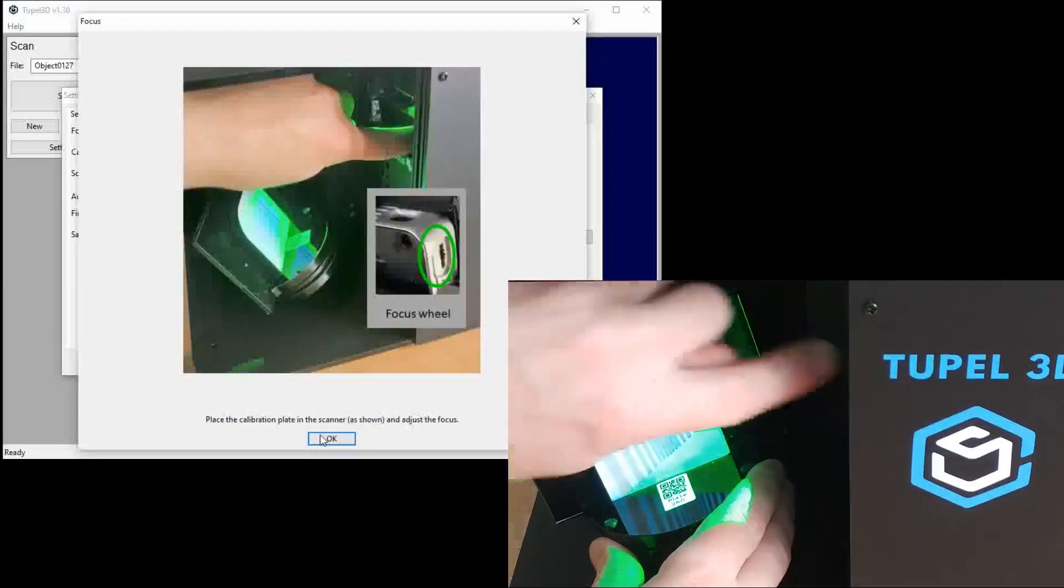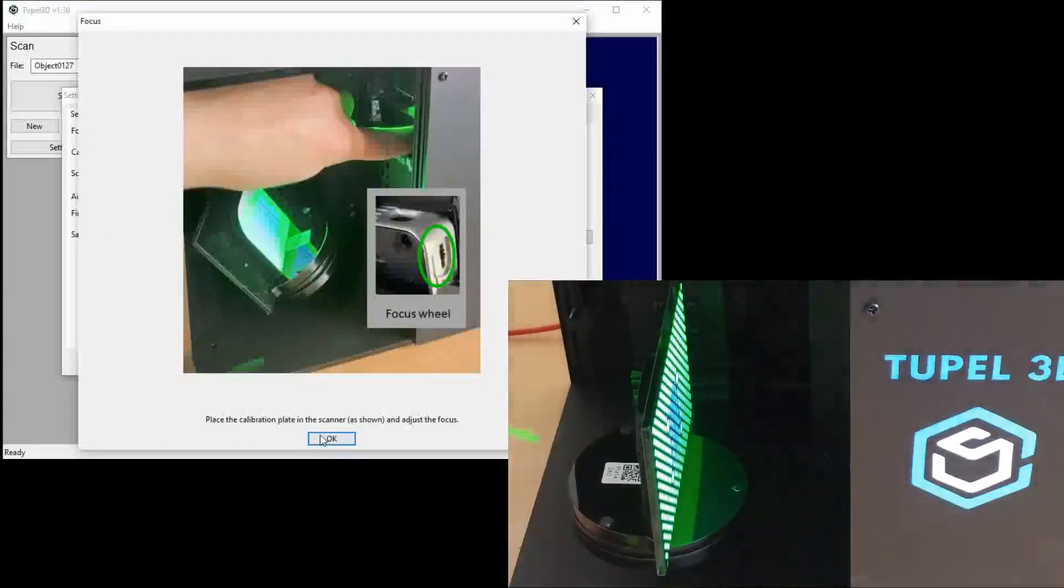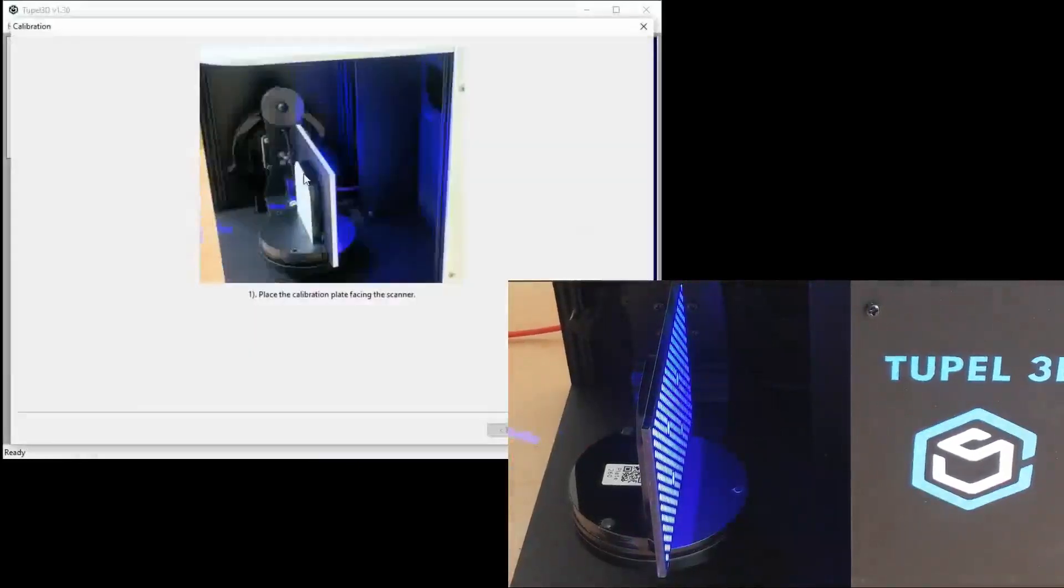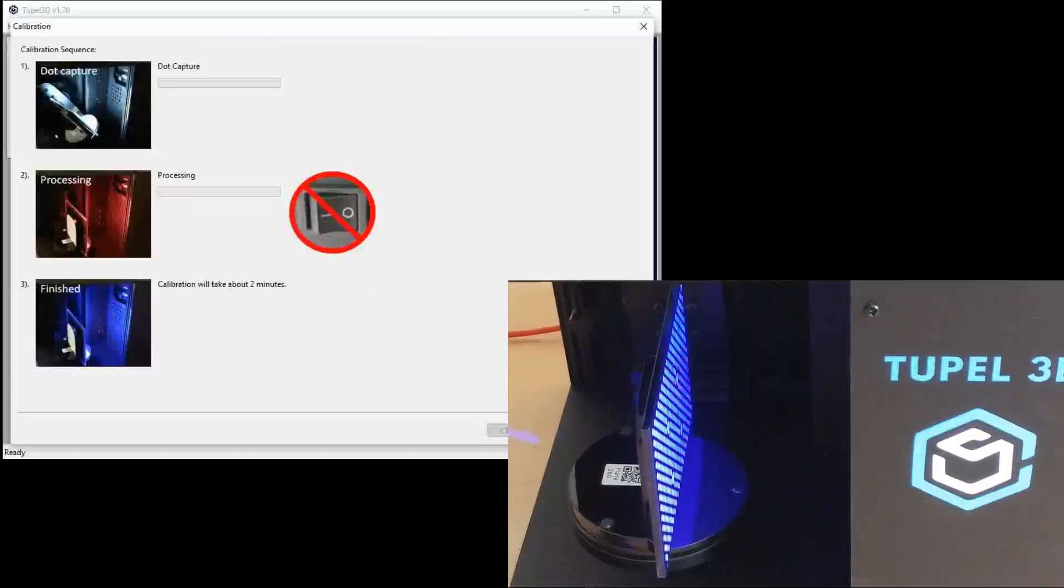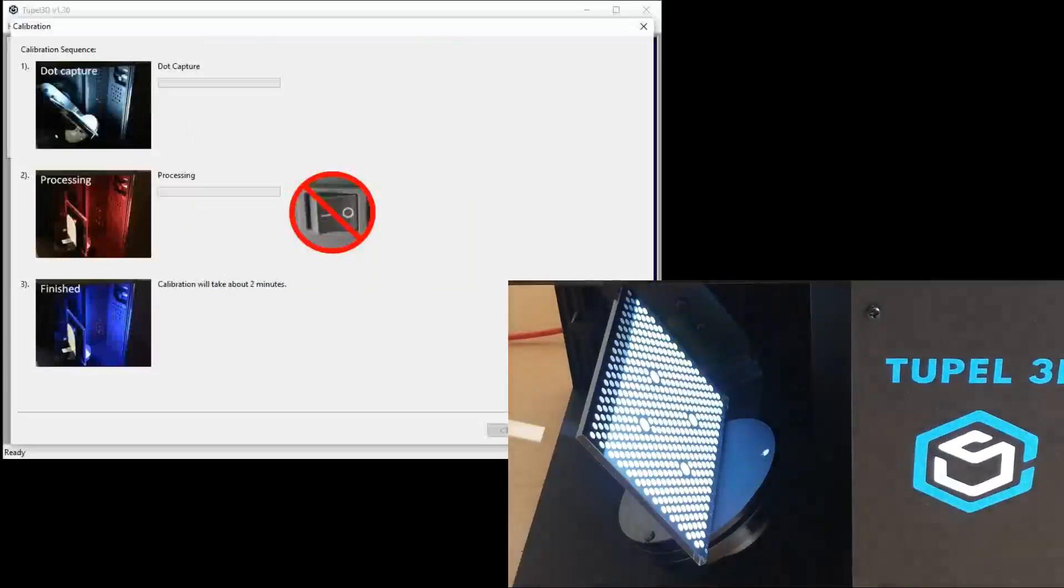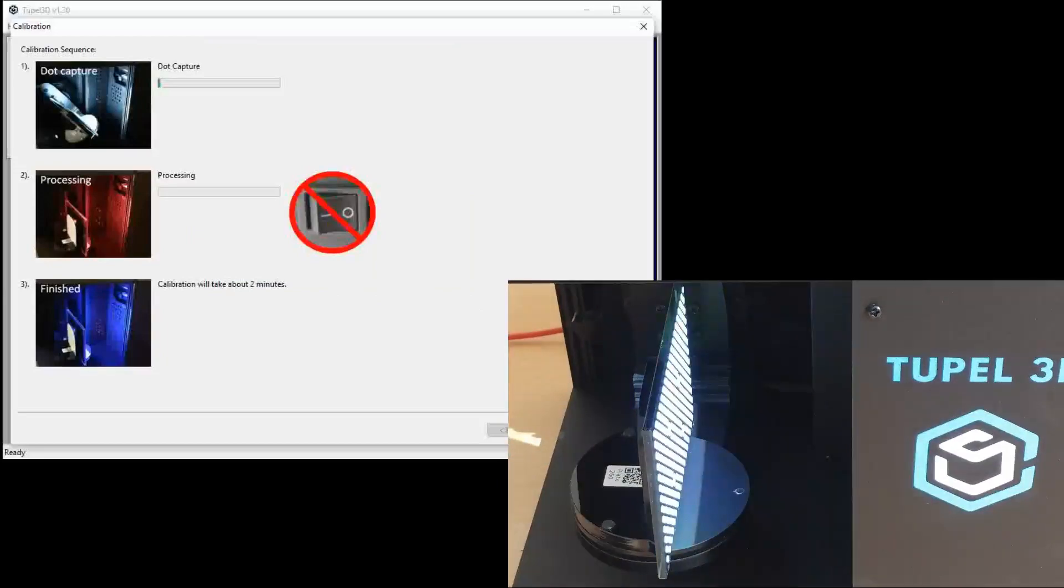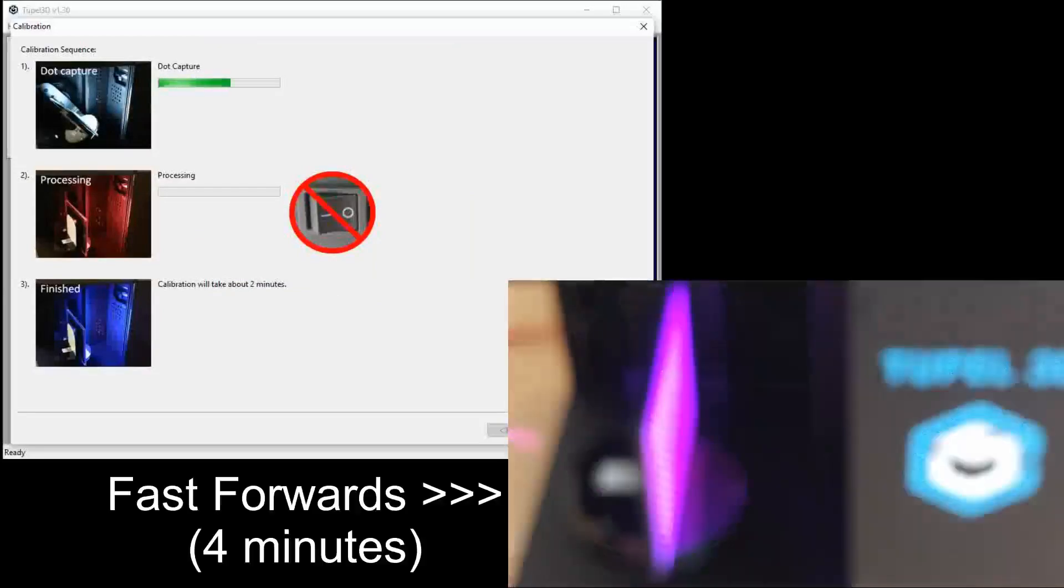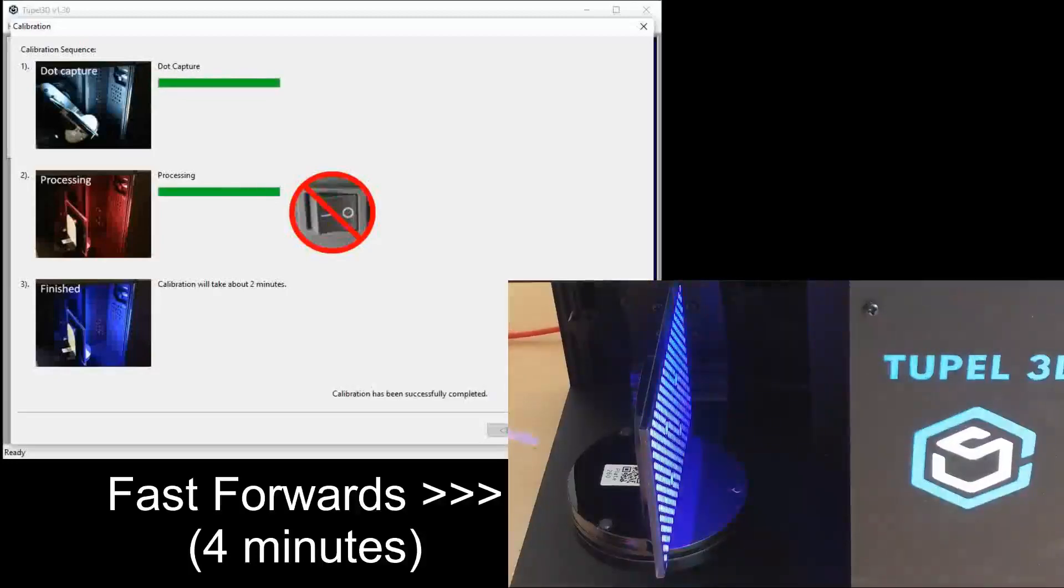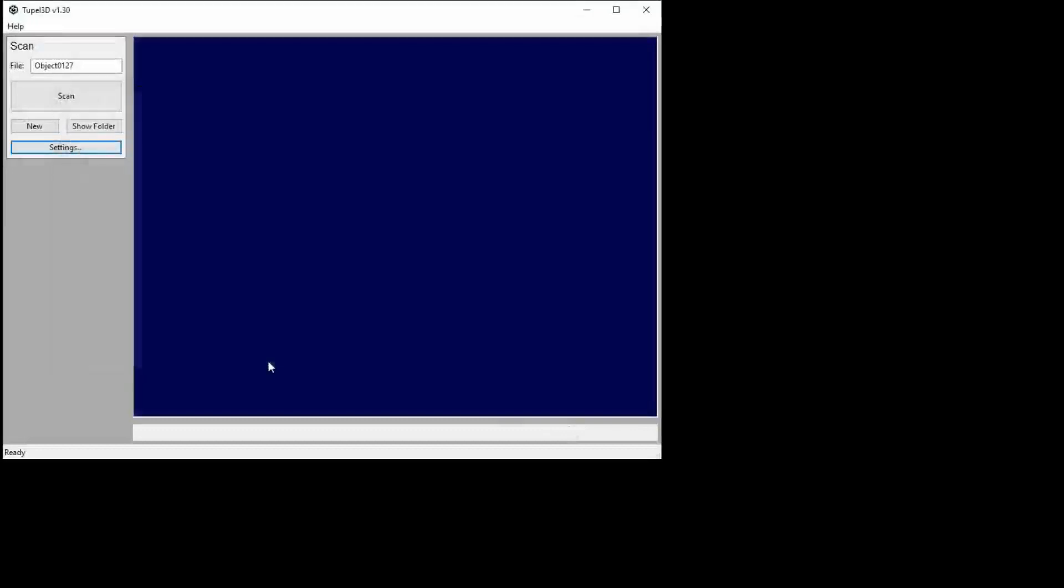And I've left the calibration plate in position, ready for calibration. So I click calibrate, and off it will go, doing its calibration dance. When it's finished, it will tell you that calibration has been completed successfully, and now you're ready to scan.